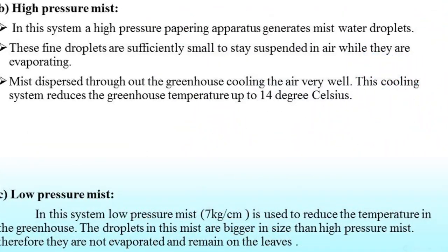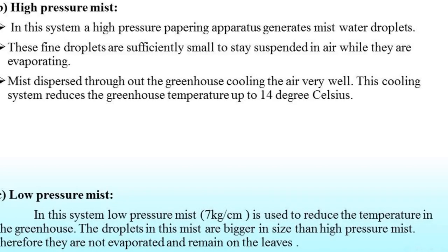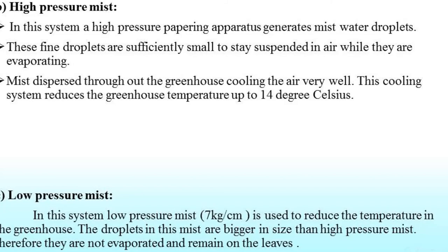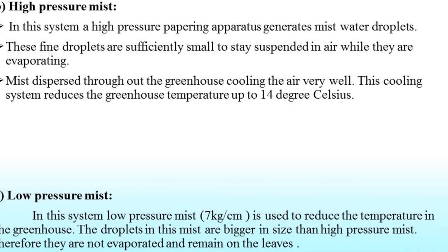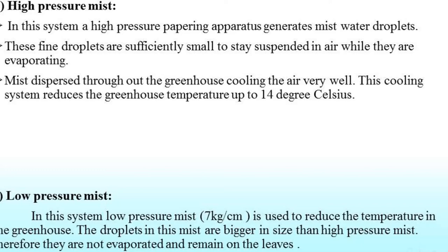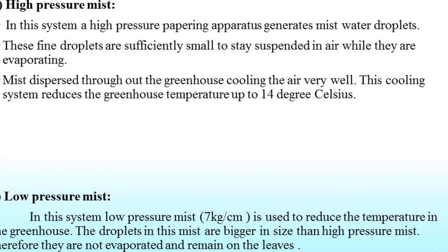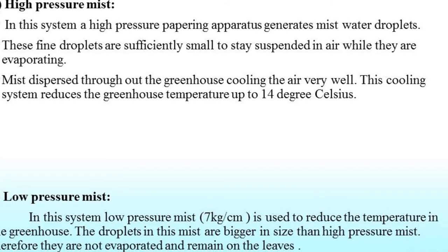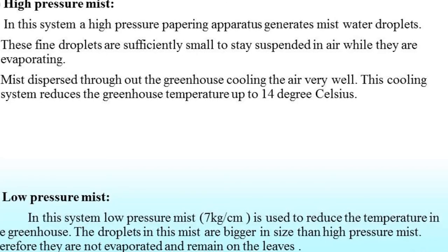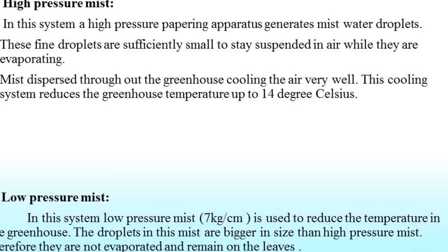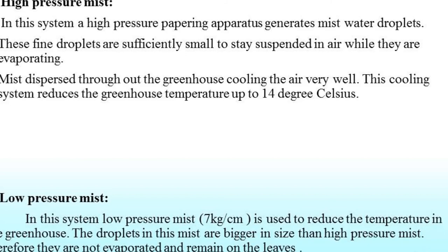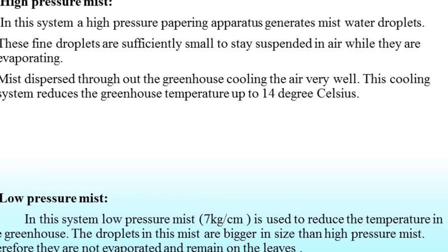The second evaporative method is high pressure mist. In this system, a high pressure apparatus generates fine mist water droplets. These fine droplets are sufficiently small and stay suspended in the air while they are evaporating. The mist droplets are dispersed throughout the greenhouse and cool the air very effectively. This cooling system reduces greenhouse temperature up to 14 degrees Celsius.